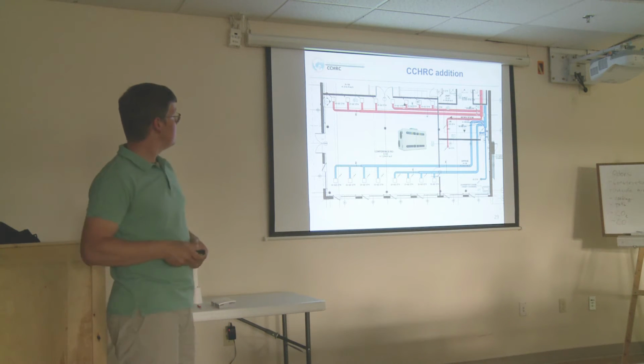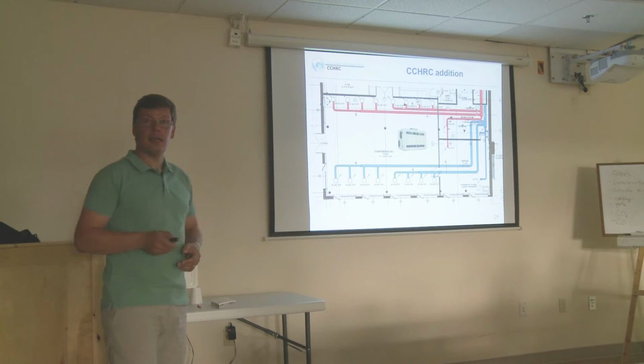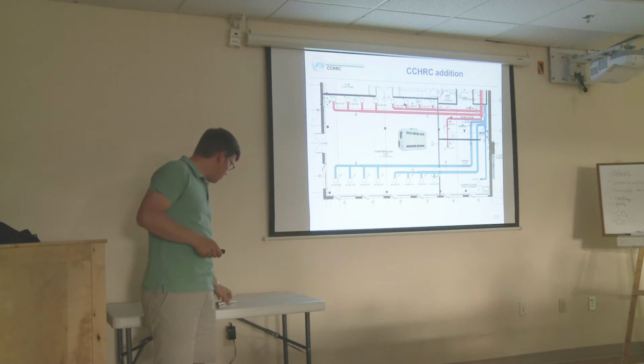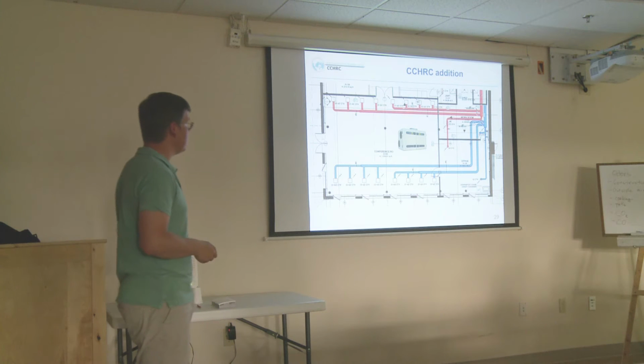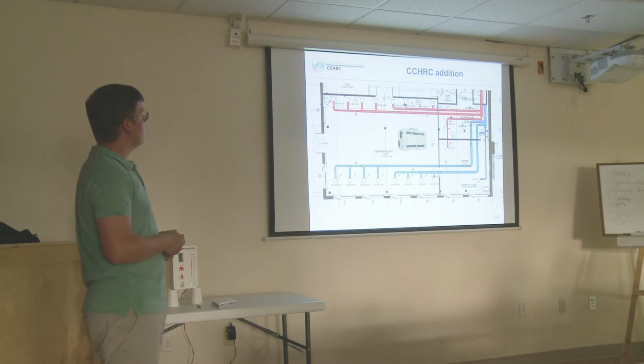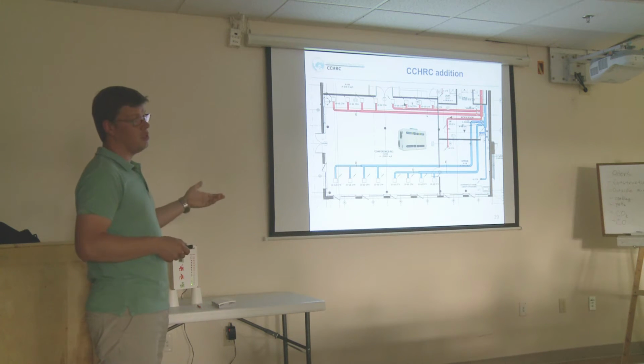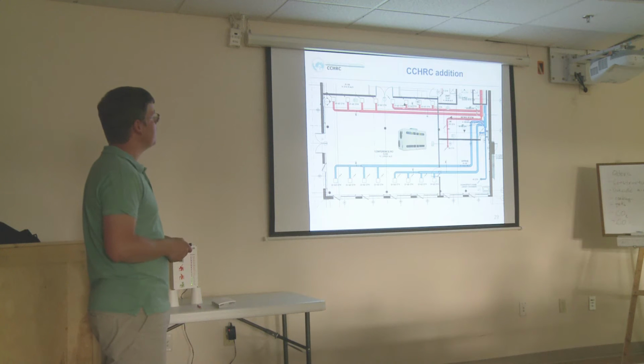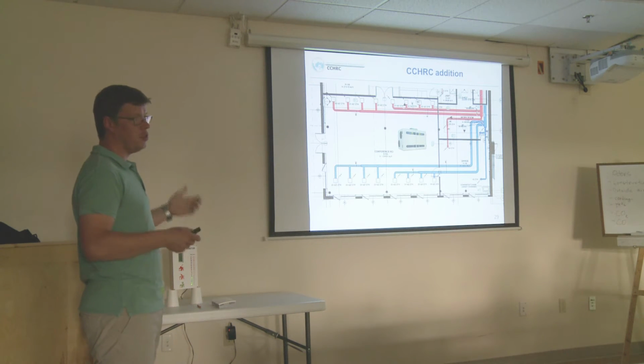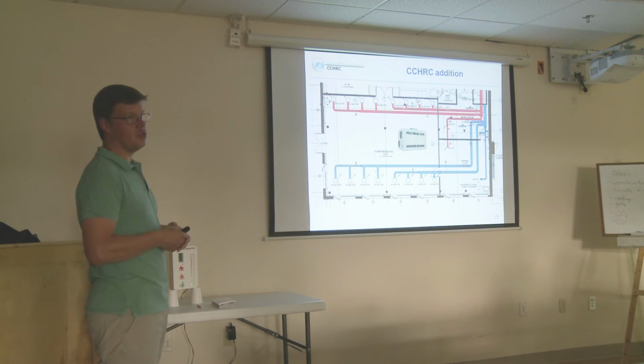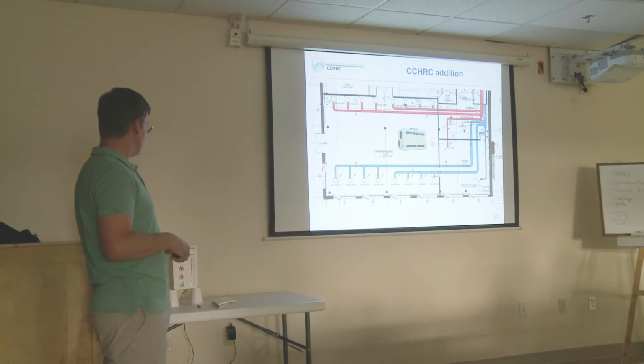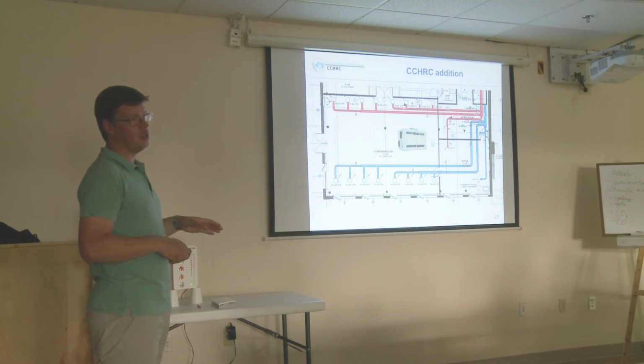Then the same with the exhaust, and we have 2 CO2 sensors which are now plugged off. Once one of them senses elevated CO2 concentration, it would open the dampers on that particular branch, one half or the other, and send a signal to the ventilation unit to boost up the ventilation. Right now, since the sensors are off, there's no ventilation in this room.